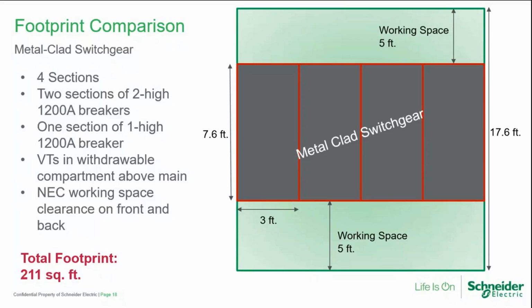NEMA or NEC required working clearance in the front and in the back. So if I'm looking at the total footprint for switchgear plus NEC required working space, I'm looking at 211 square feet of space for this 15 kV application.